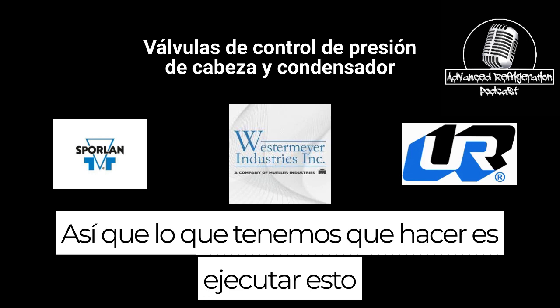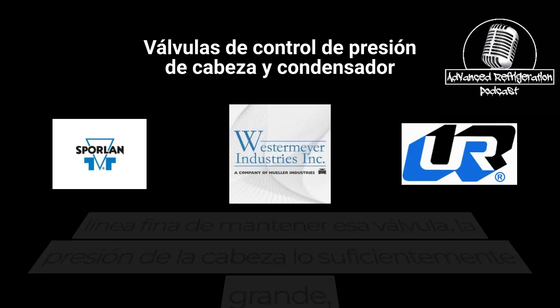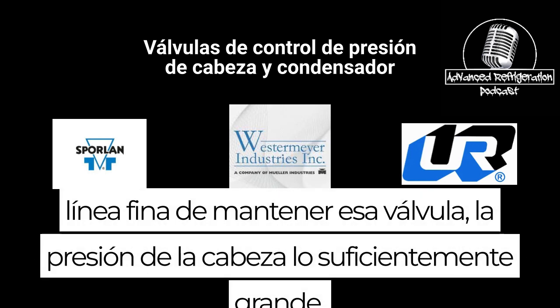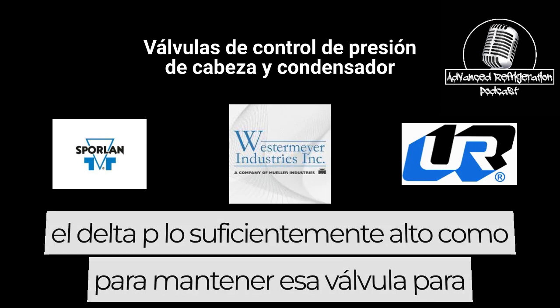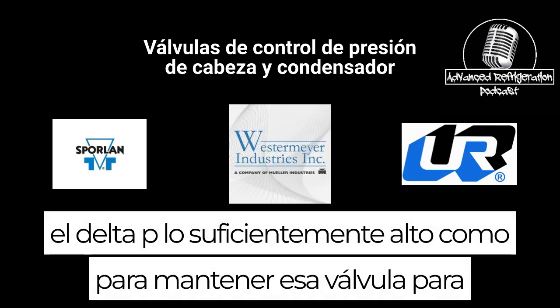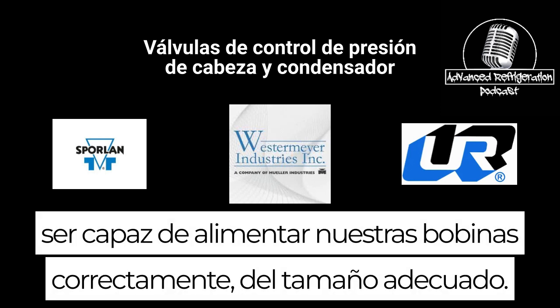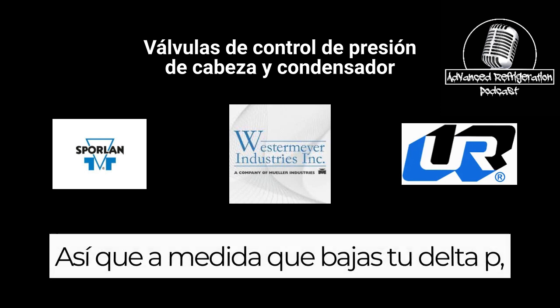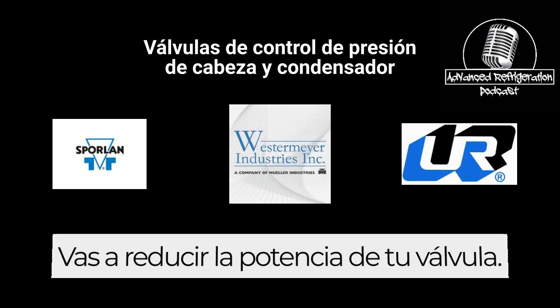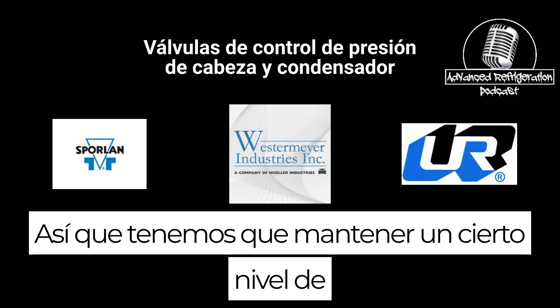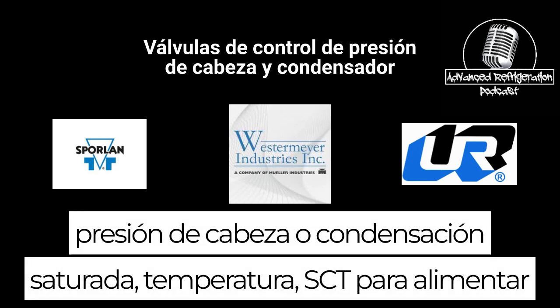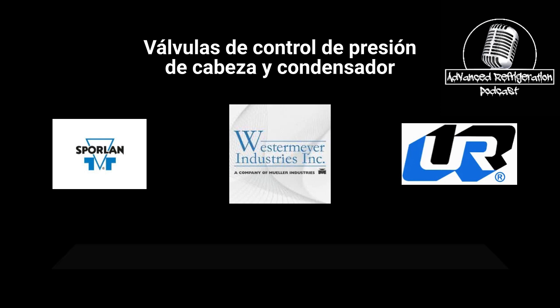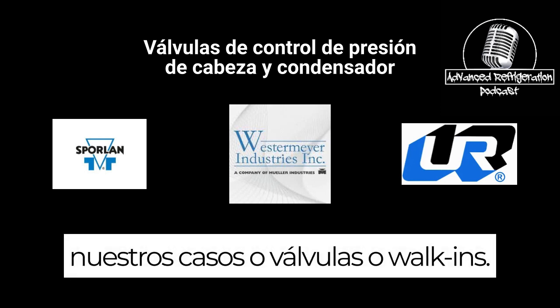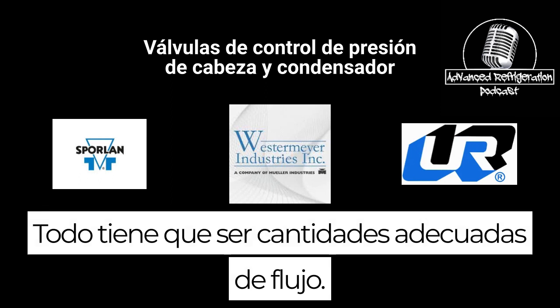So what we have to do is run this fine line of keeping that head pressure up large enough, the delta P high enough, to keep that valve able to feed our coils properly sized. So as you lower your delta P, you're going to derate your valve. So we have to maintain a certain level of head pressure or saturated condensing temp, SCT, to feed our cases or valves or walk-ins. Everything has to have proper amounts of flow.